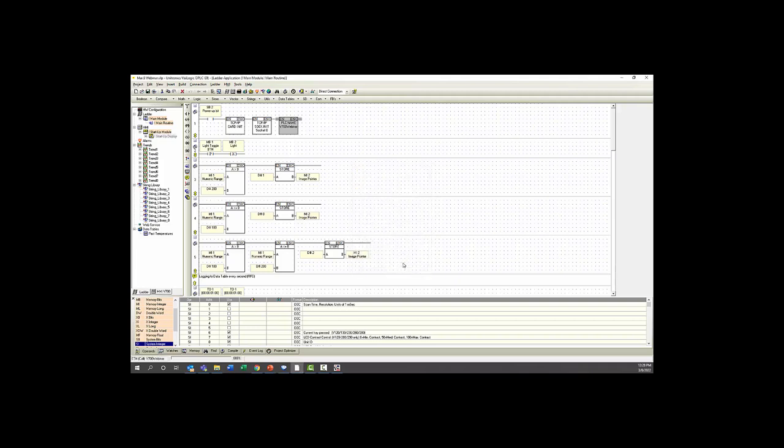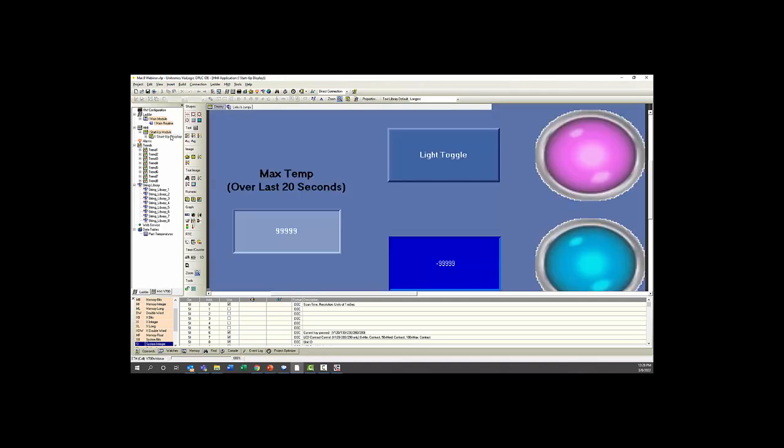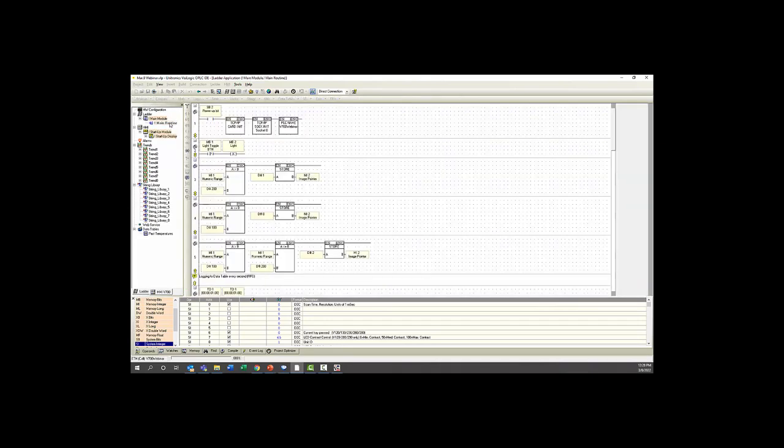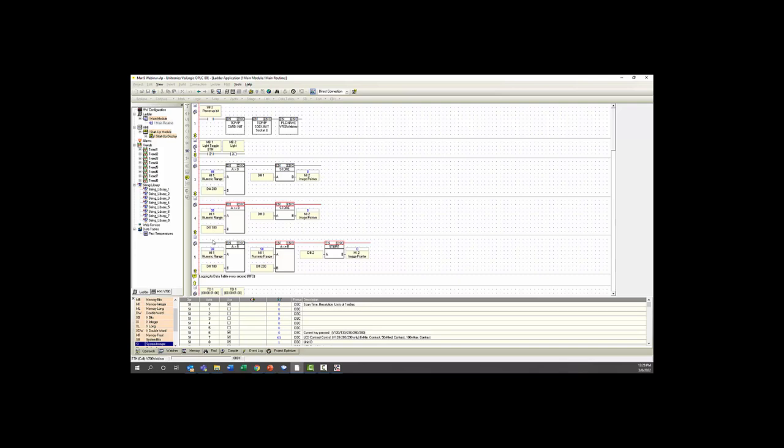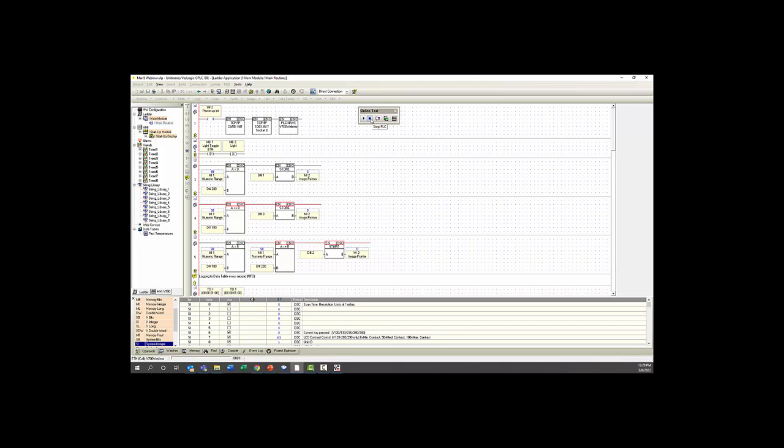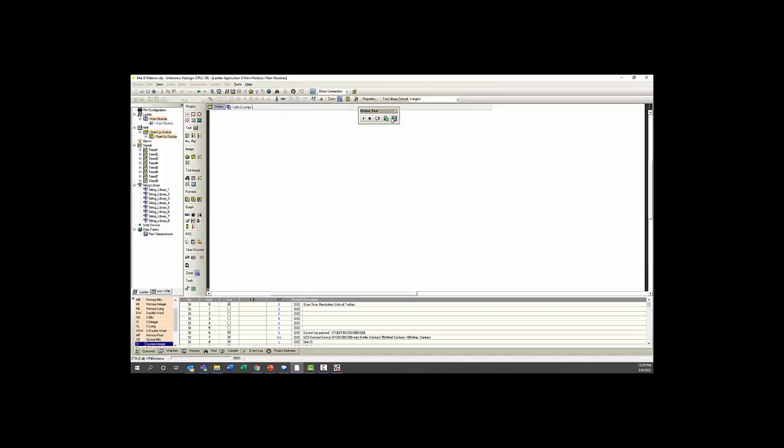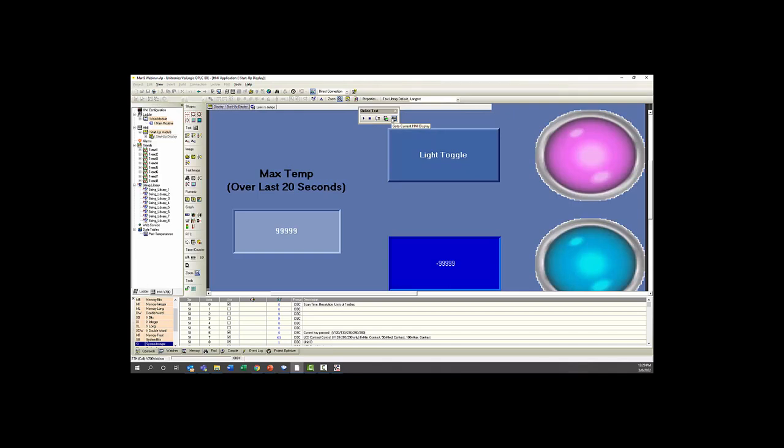Just like the Unistream, you can go ahead and you can press the online test mode and it will use whatever connection you've set up in that prior connection menu. So when you're in online test mode, the HMI will not become grayed out, but you will see the red lines appear with the logic in your ladder. You will also see an online test block pop up, which allows you to stop the PLC, run the PLC while in stop mode. You can also execute a single cycle of the PLC at once. You can go to the current HMI display. That brings you to the active HMI. And you can press remote access, which will bring up the remote access app.